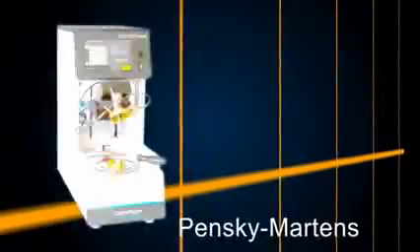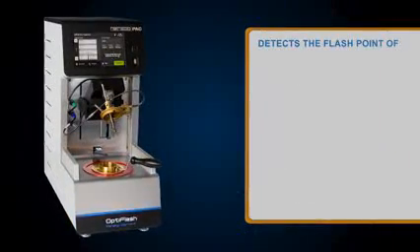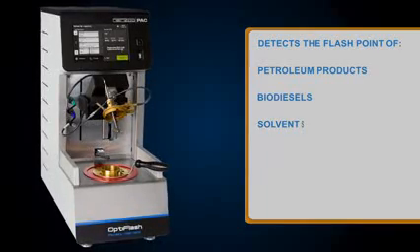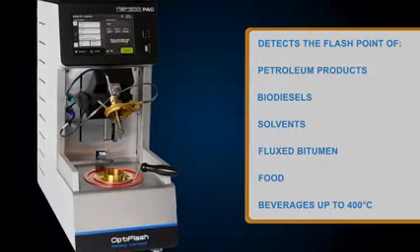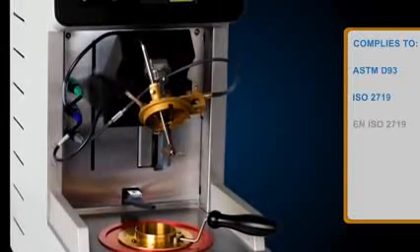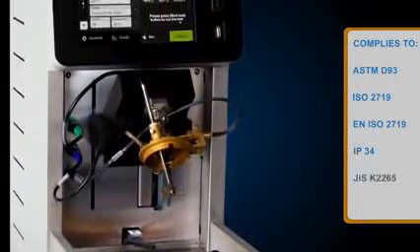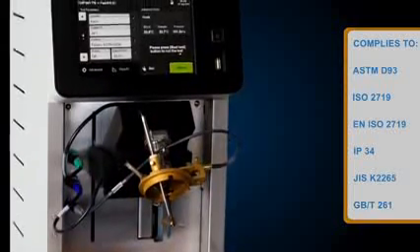OptiFlash is currently available for the following methods: Pensky-Martens, TAG and ABEL. The OptiFlash Pensky-Martens model detects the flashpoint of petroleum products, biodiesels, solvents, fluxed bitumen, food and beverages up to 400 degrees Celsius. It complies with leading global standards such as ASTM D93, ISO 2719, ENISO 2719, IP34, JIS K2265 and GB/T 261.